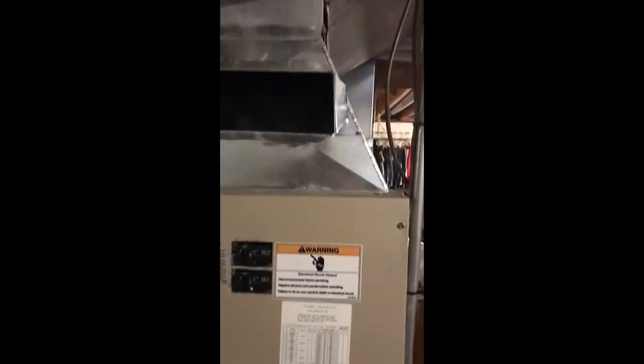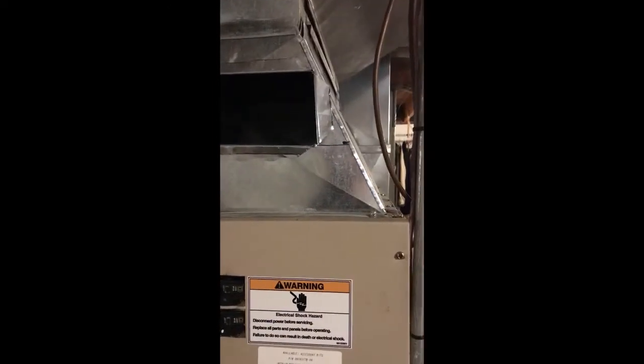Okay, I ended up using my die grinder to cut the hole in here—much simpler than trying to use the tin snips, and more accurate. What I did is I left a half inch overhang on the actual size of the heat exchanger, and bent them back to give the plenum some rigidity, keep it rigid. I just trimmed off these ears a little bit so I don't have sharp edges here, and then the foil tape will also go around there to seal it.